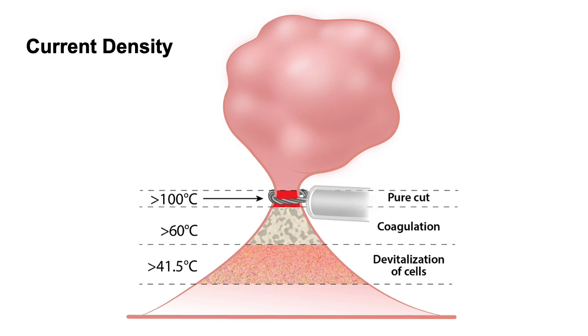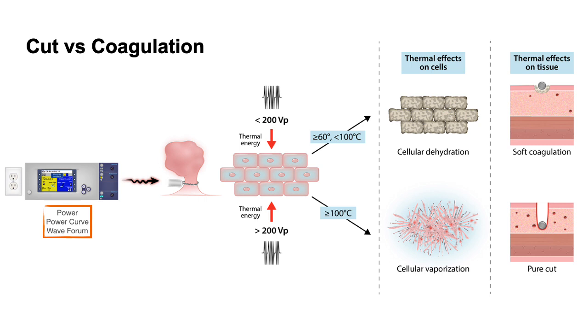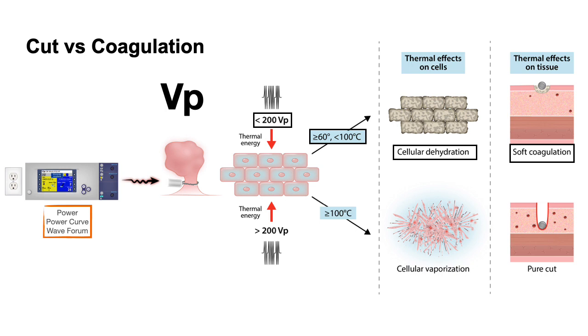Now, let me introduce you to two concepts that are used in electrosurgery: cut versus coagulation. This is dependent upon the voltage that drives through the tissue. Let us first look at coagulation. Coagulation is typically done when you keep the voltage below 200 volts, and that results in a slow, simmering heat that results in cellular dehydration and soft coagulation. The same effect could also be achieved by a higher voltage when you interrupt the cycles with a 6% duty cycle or a little bit higher. We will talk about it in a couple of seconds.